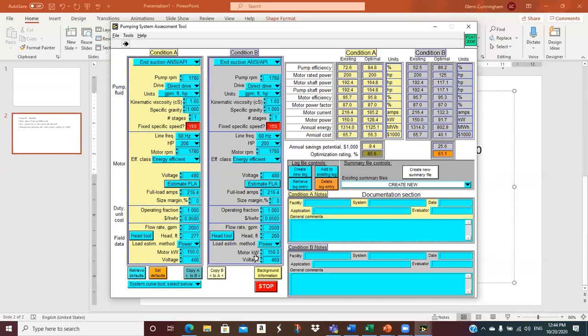But I have to somehow project what the power is going to go to, because I've still told it I'm using 150 kW. Well, if I'm generating 77 fewer feet of head with a pump, my power should fall. Now, then you got to come up with a way to predict that. One thing you can do, you can look on the pump curve and see what the efficiency should be.